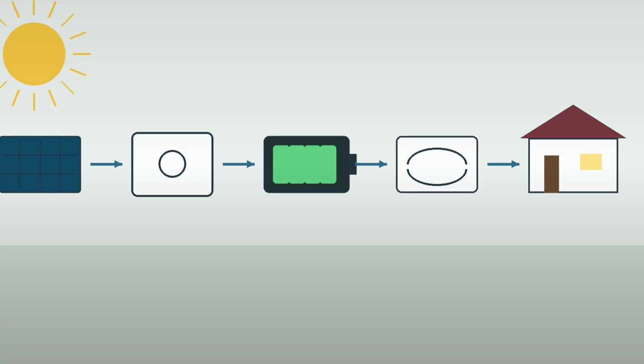Maintenance is simple if you schedule it. Monthly, check for loose terminals, corrosion, damaged insulation, animal damage, blocked ventilation, water intrusion, and unusual heat marks. Seasonally, clean panels if dirt or pollen is cutting production, check mounting hardware, verify controller settings, test the low voltage cutoff behavior, and compare daily production against your expected seasonal range.